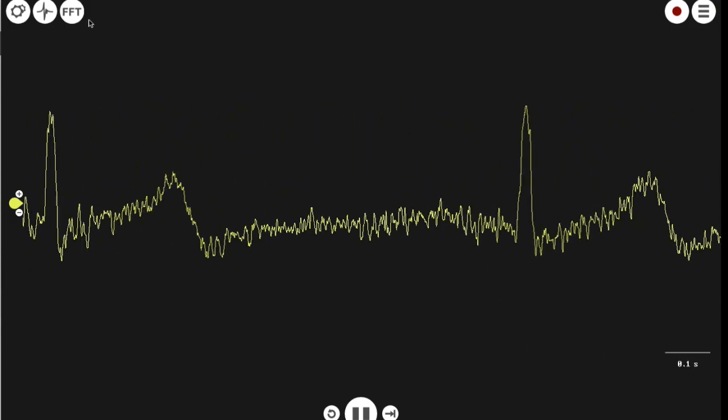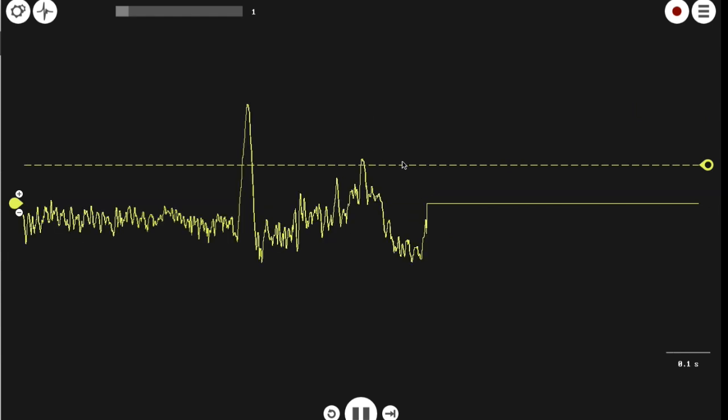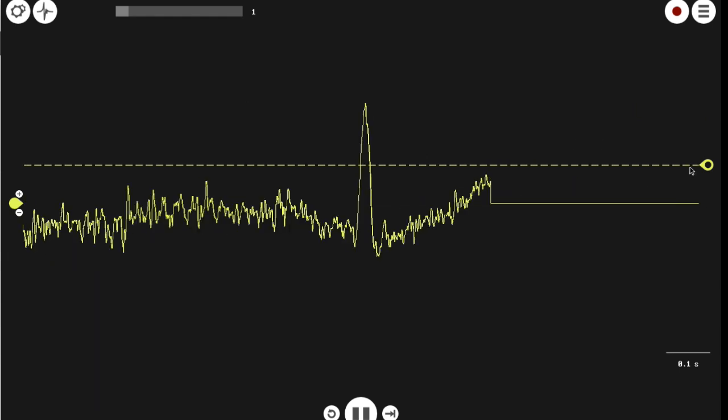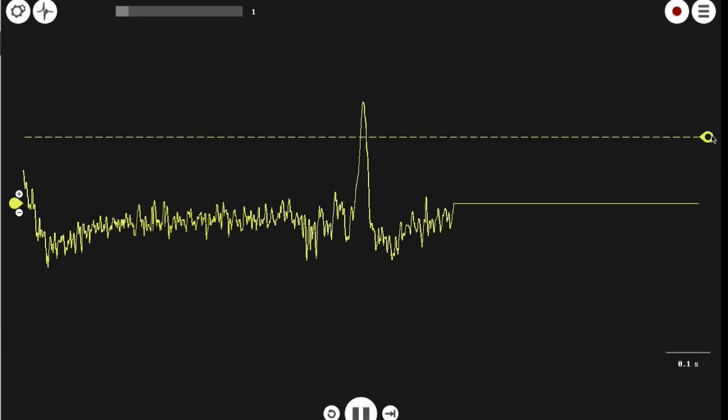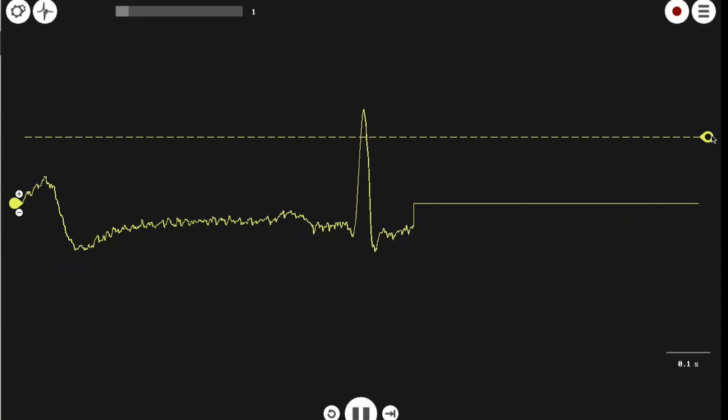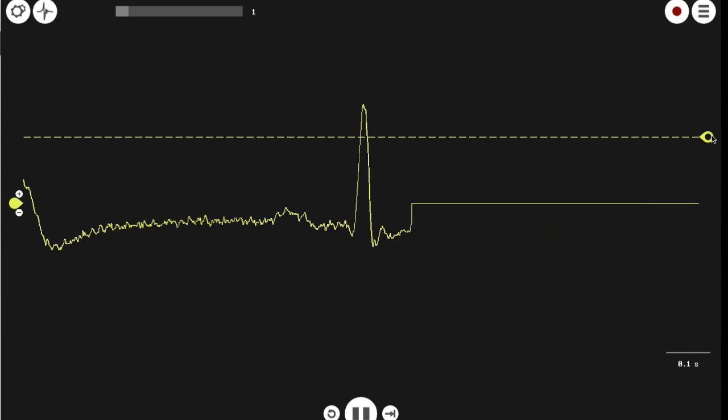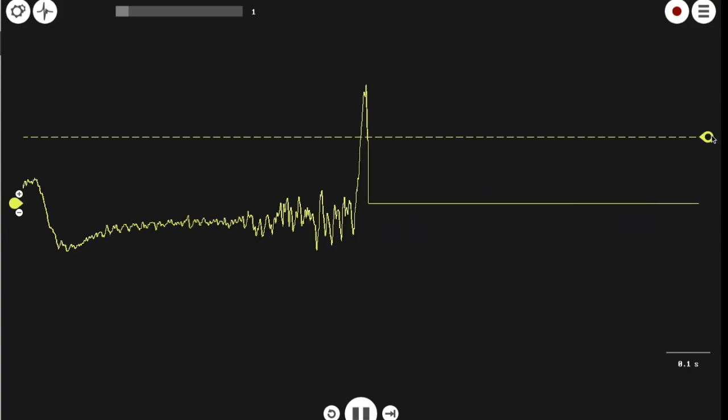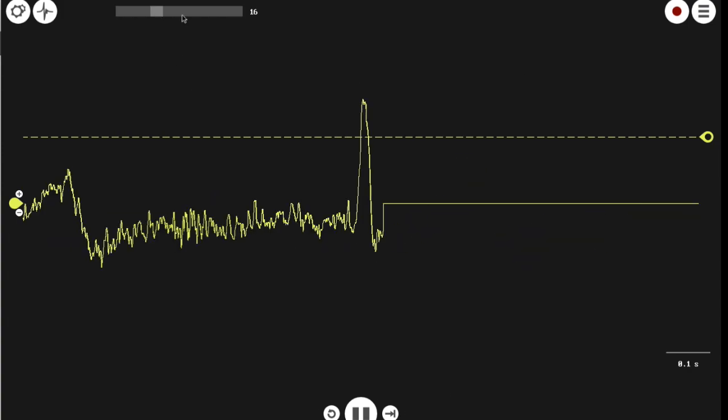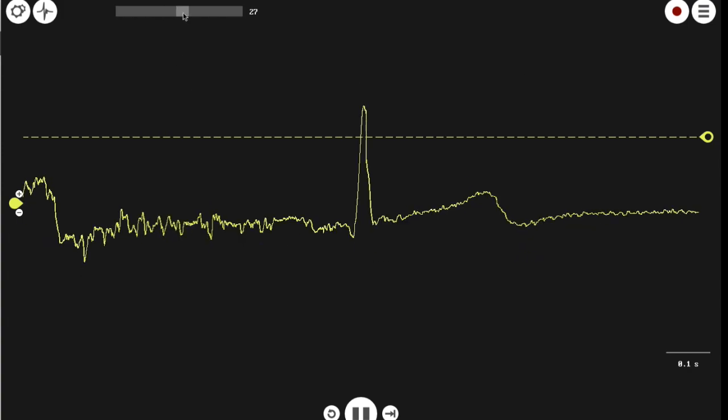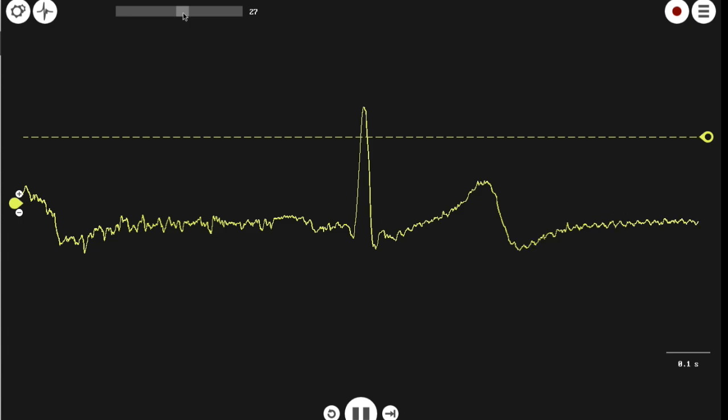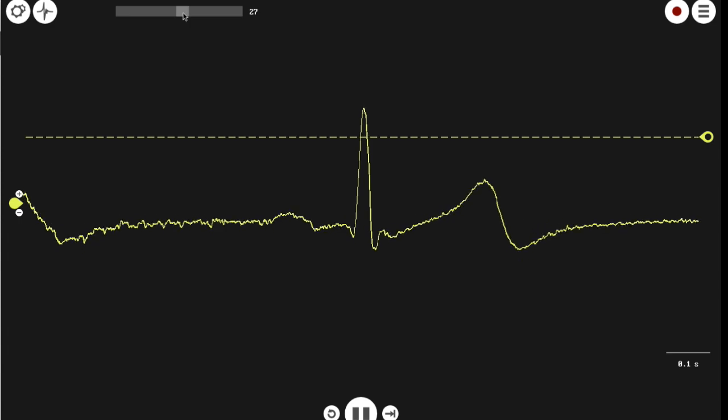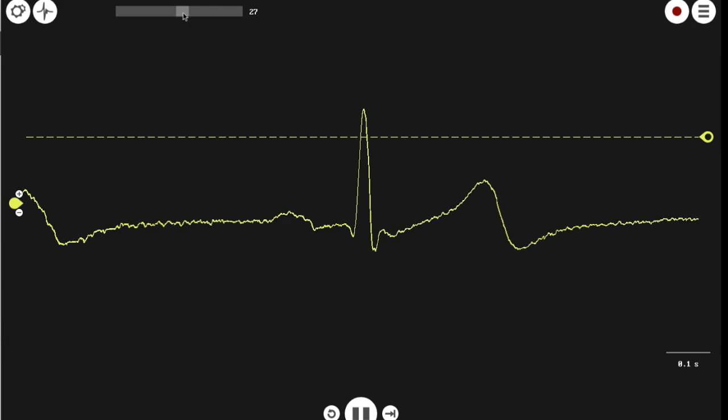Do you want to take a threshold? Of course you do. You can do this by clicking on the threshold button in the upper left hand side of the screen. This will momentarily freeze the recording when the signal crosses the threshold line that you set. And we know you want to average the signal, which you can certainly do by moving the slider bar. This will change the number of times the signal is averaged together so you can get a waveform that looks very much like the iconic waveforms you see in your textbook.